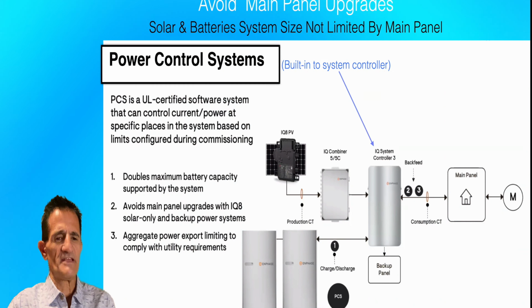Enphase also offers a system controller that includes a power control system. Often, especially in older homes or homes that aren't all electric, the main panel can't handle the desired solar and battery system size needed to cover your electric use. Upgrading that main panel can cost thousands of dollars and get complicated. To avoid that cost, Enphase built in this power control system, which regulates how much electric is fed to and from your main panel so it's never overloaded beyond its rating. This is set up by the solar installer.